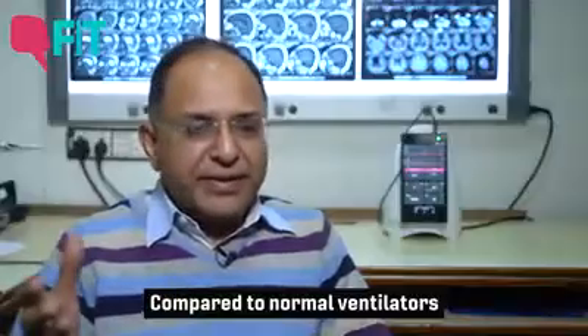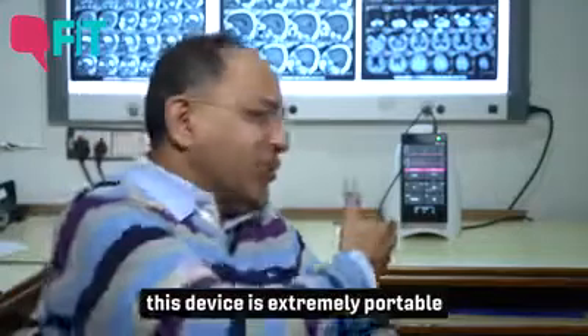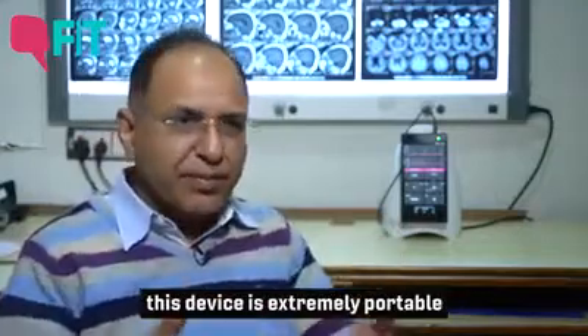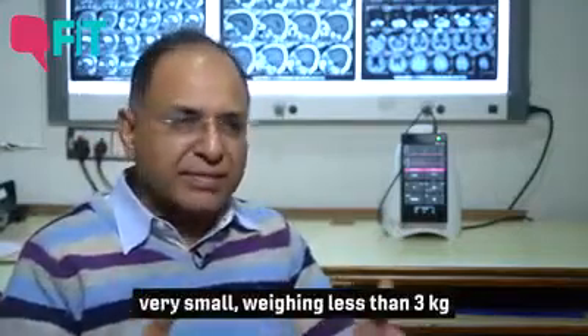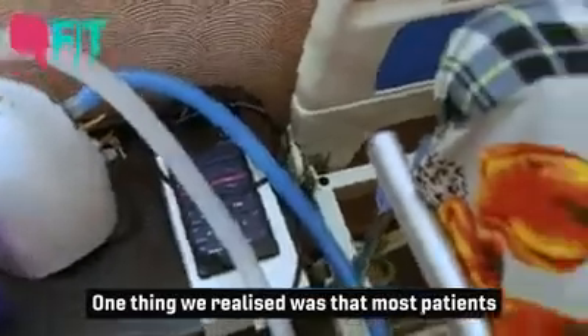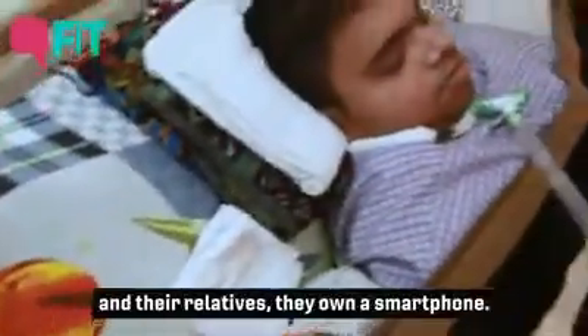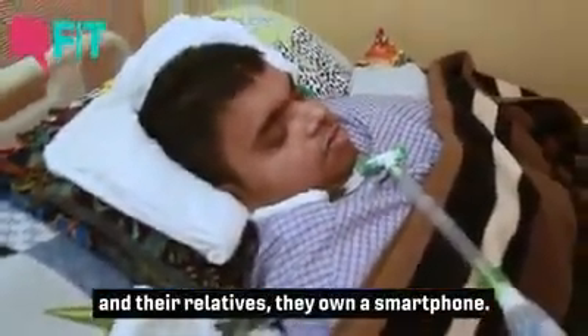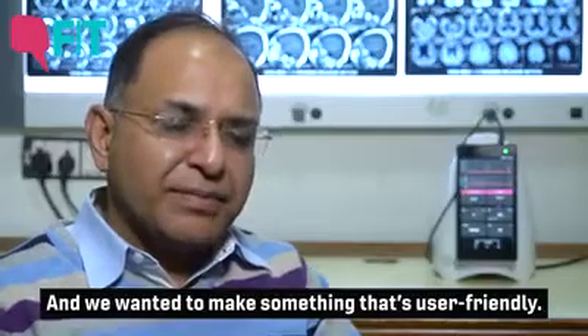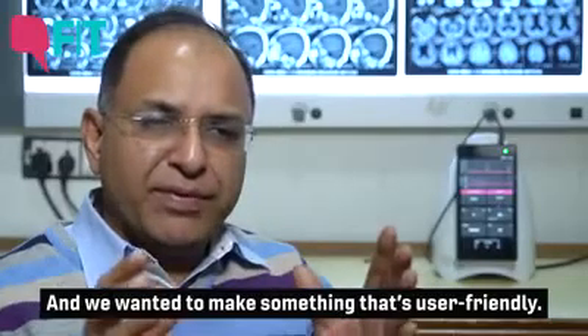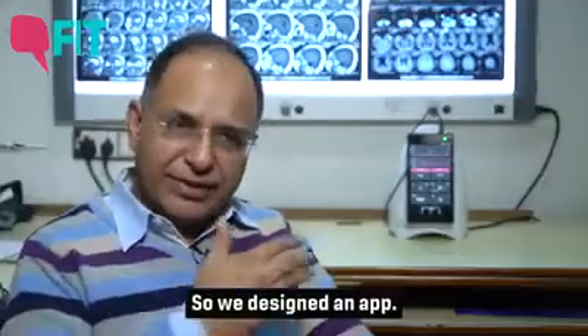Compared to normal ventilators, this device, if you look out here, is extremely portable, very small, weighing less than 3 kgs, and it runs off an Android phone. So one thing we realized was that most patients and relatives own a smartphone, and we wanted to make something which was very user friendly. So we designed an app.